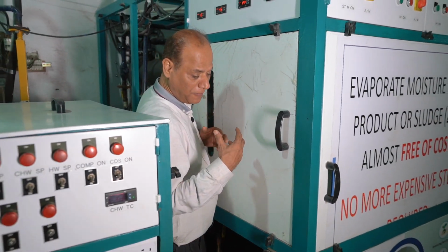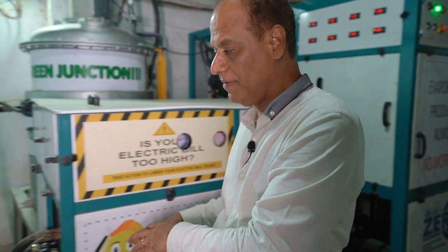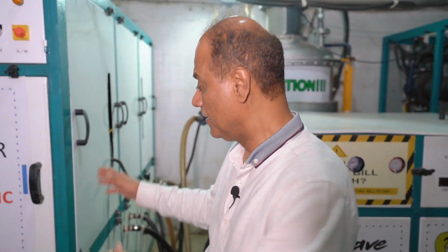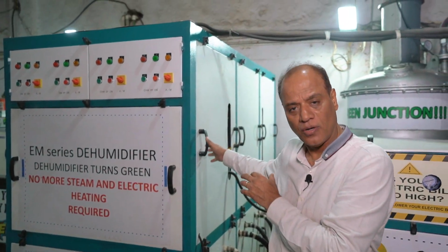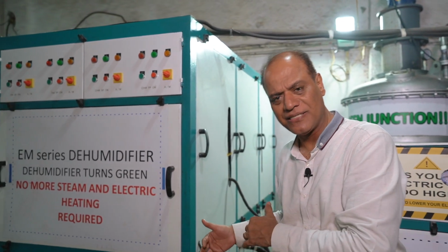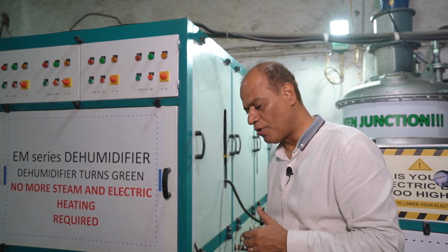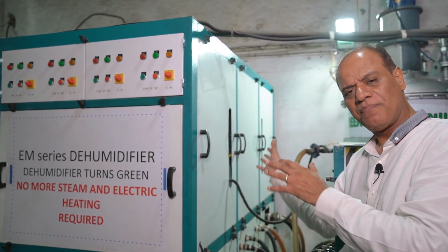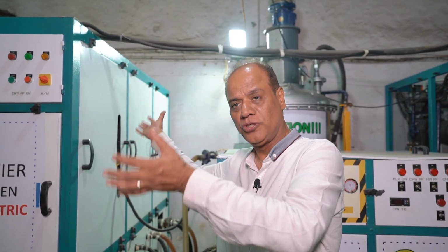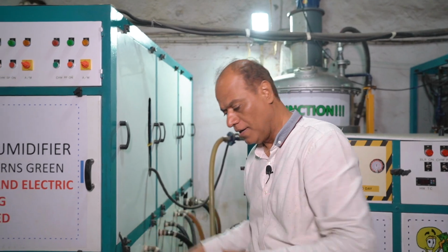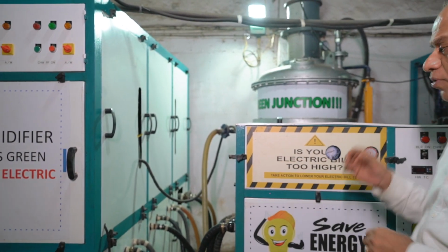So in this beautiful arrangement, whatever chill water is generated and whatever hot water is generated, we have tanks here. There is a hot water tank, there is a chill water tank. In the hot water tank, we have primary circuit pumps, secondary circuit pumps, and on the chiller side, we have primary chill water pump, secondary chill water pump. So this is nothing but a plant room which has tanks and pumps, having all the basic configuration of the machine which is transporting chill water and hot water.